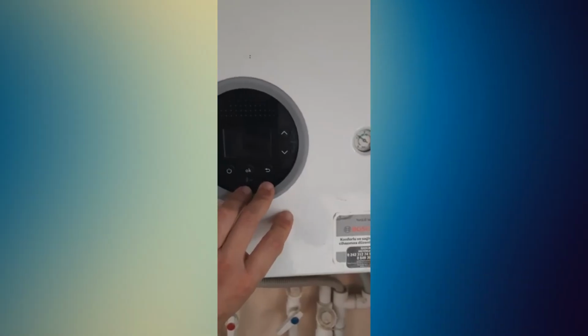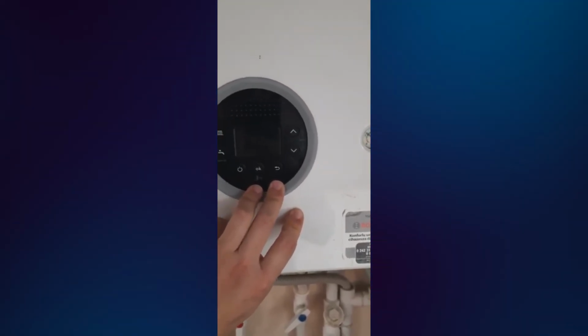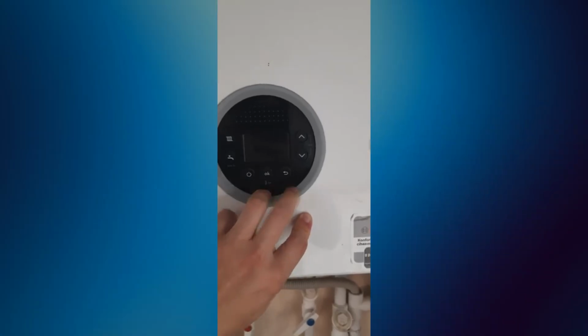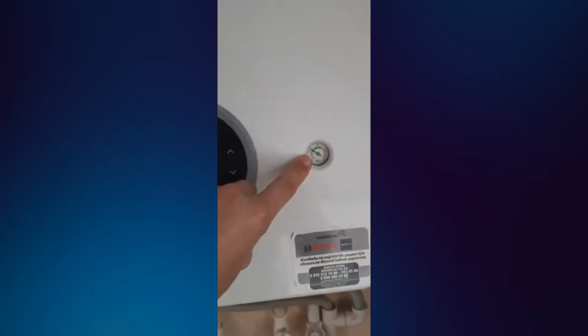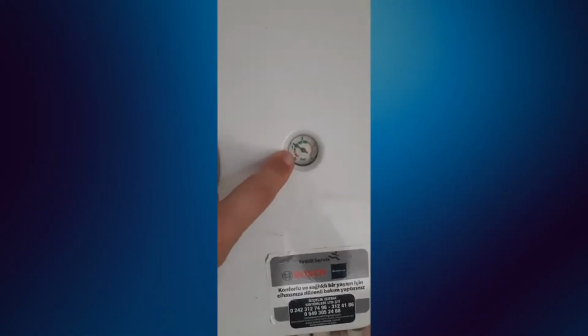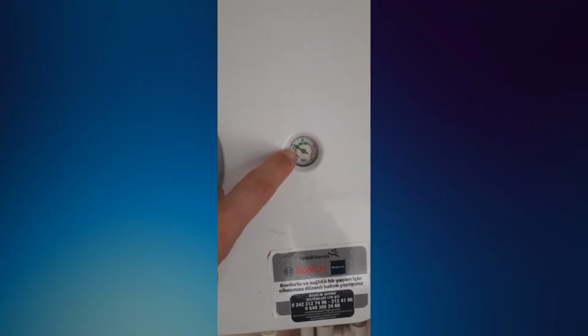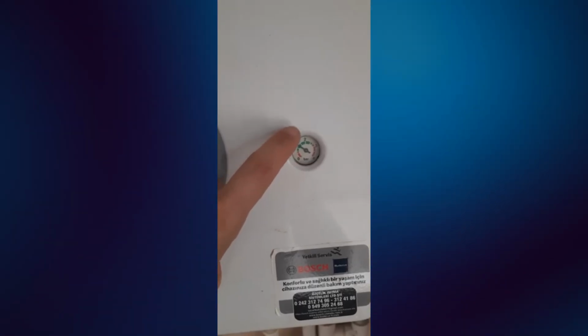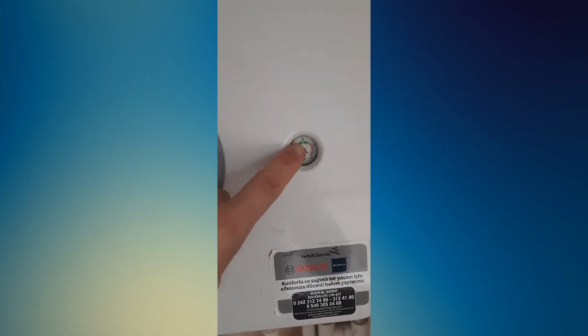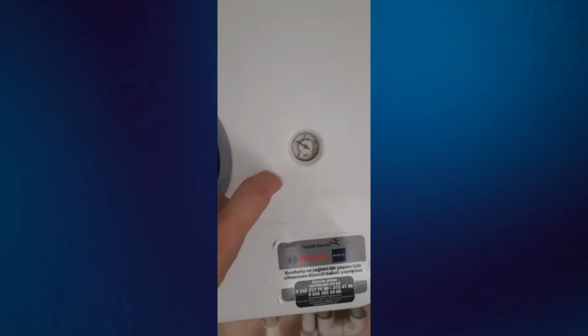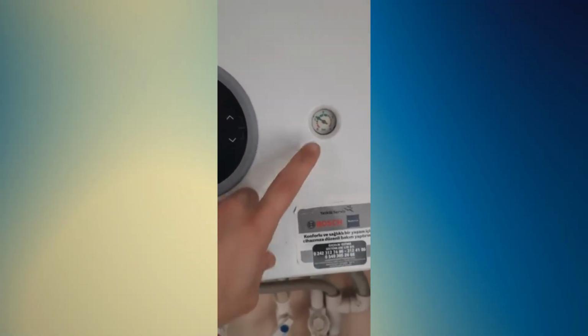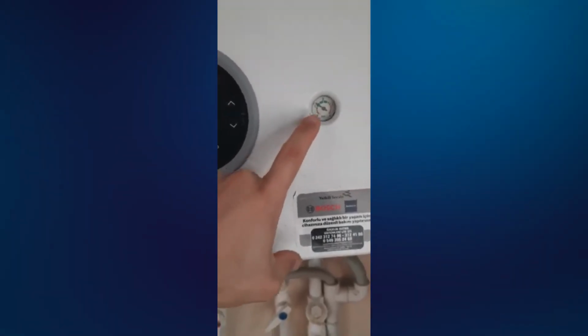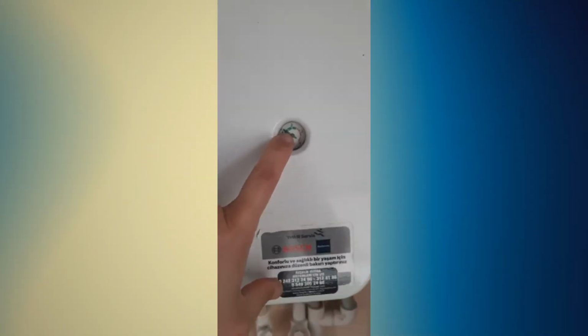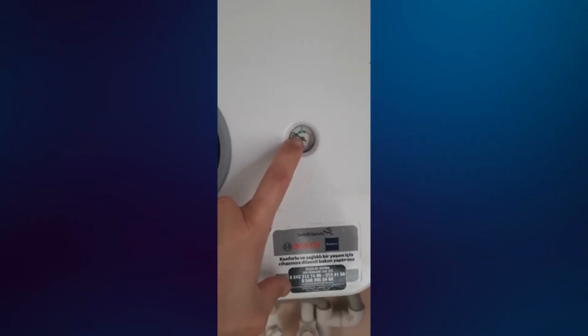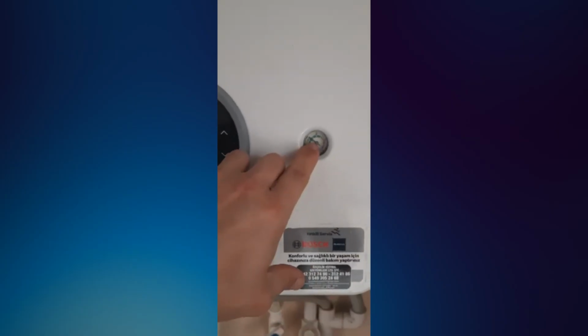There are safe checks a homeowner can do, but most internal causes of error 2951 need a qualified heating engineer. Let's start with the safe checks. The first thing to check is the boiler pressure. Look at the pressure gauge or digital pressure reading. On many sealed central heating systems, the normal cold pressure is usually around 1 to 1.5 bar. Some systems may be slightly different, so the manual for your exact boiler is always the best reference. If the pressure is very low, the boiler may not operate correctly. Low pressure can also cause other faults or make an existing problem worse.